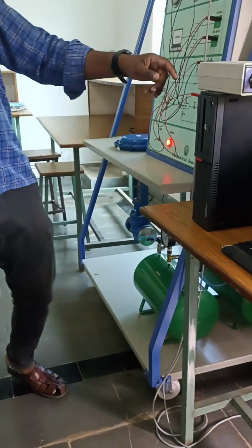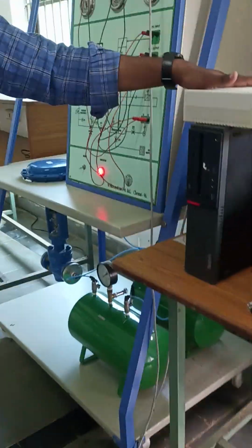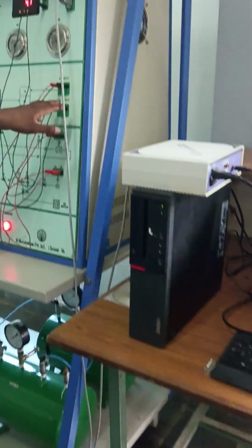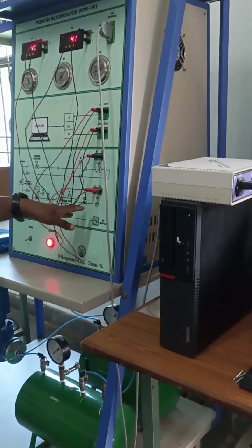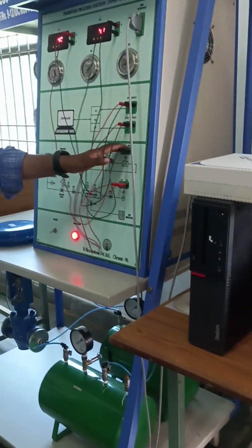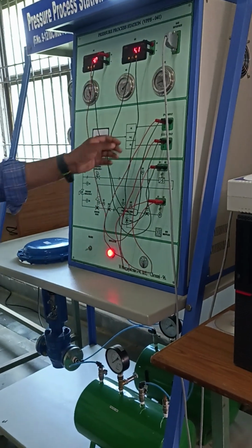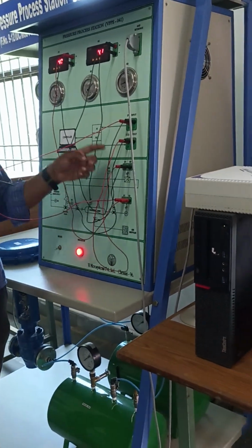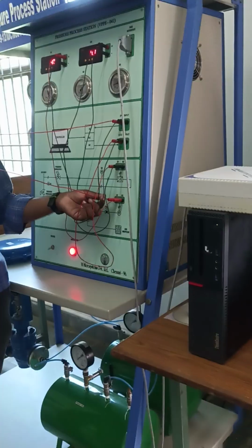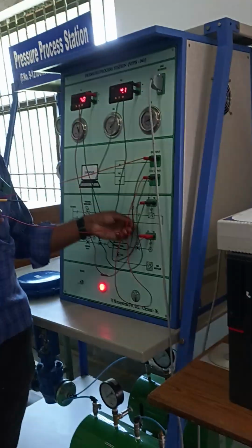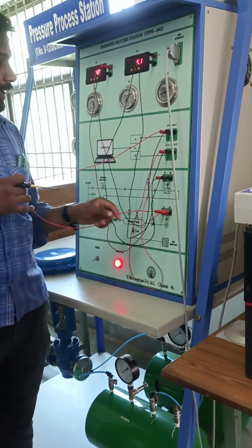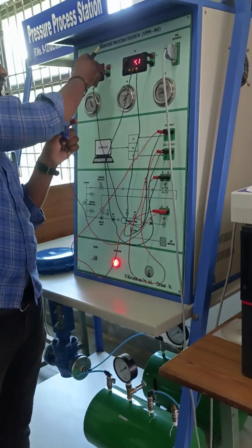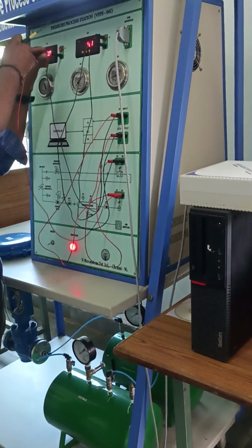So that will come to the PV of your controller, and then CO is the controller's output. For that control output, it will go to the I to P converter. So like that, it will be patched here. For PV, it will be giving the pressure transmitter output.